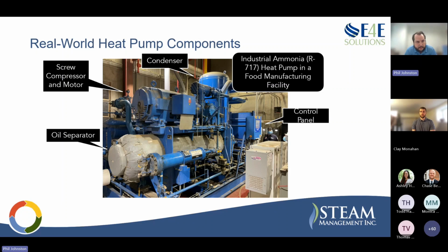This is a picture of a real live heat pump at a dairy factory that we did work with in the last year. You see some of the major components. Usually that screw compressor and motor sit on the top of the package there. This one actually has a remote evaporator, so the evaporator is not on the skid here. But you always have a control panel there with a screen to look at all the different inputs and outputs. We'll get more into that on the next slide.